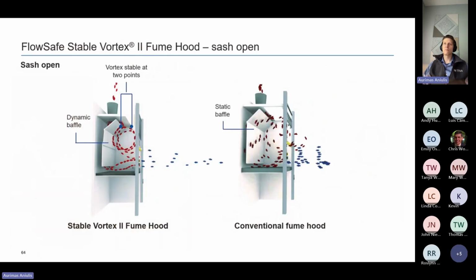Having said that, what defines a safe condition? How do we ensure a safer, better way of running a fume hood? One of those ways is a stable vortex. It's pretty much impossible to get laminar airflow inside the workspace of the fume hood because of all the Bunsen burners and grills they put in there to hang all the equipment and so on. Even the geometry of the hood, in some of these traditional hoods, was never really intended for laminar or cohesive airflow patterns to ensure containment, because it was made by lab furniture people. They didn't know about air.